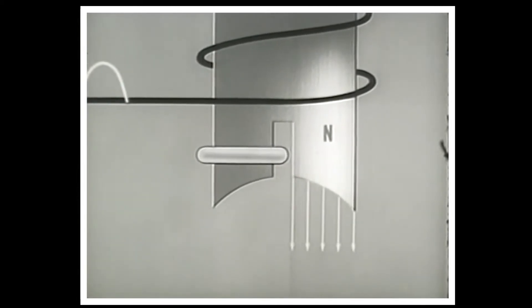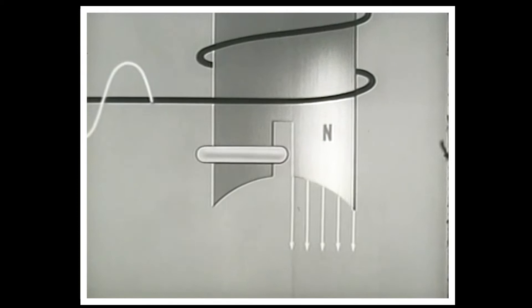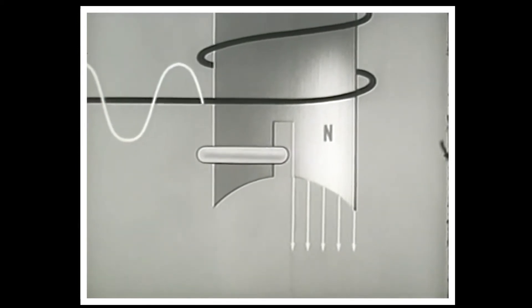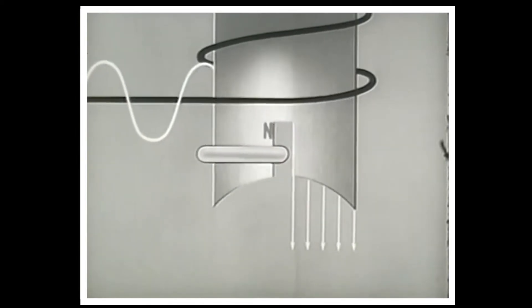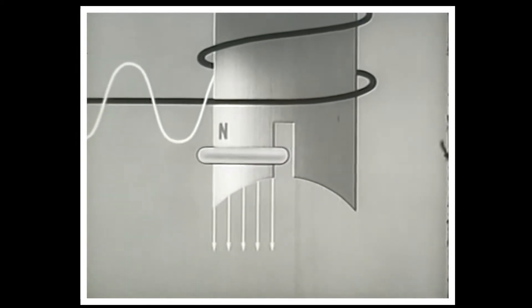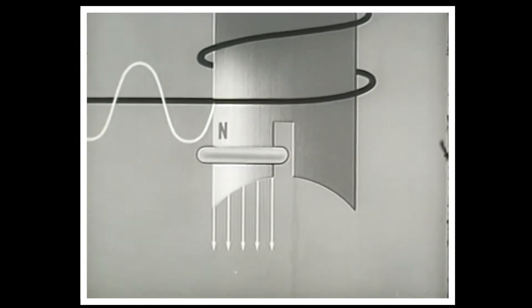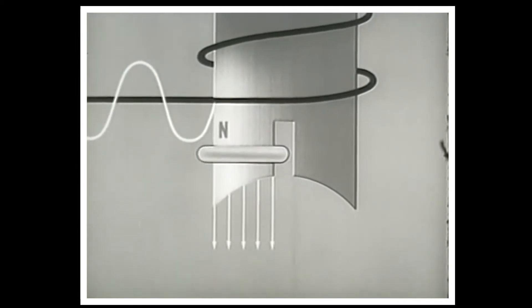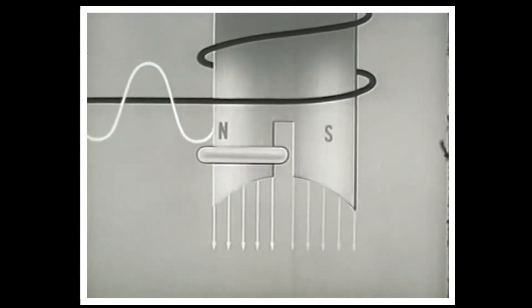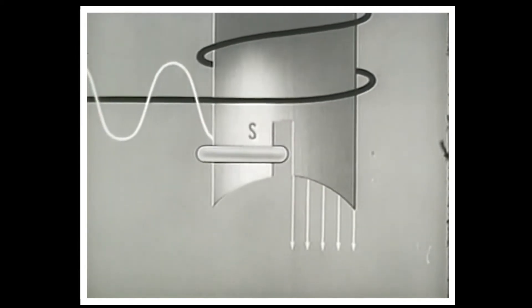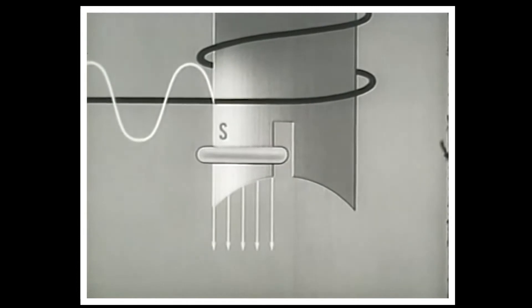Lines of force will emerge from the unshaded section of the pole face first. The inductance caused by the ring makes the shaded portion of the pole lag behind. This alternating pulsating action creates a phase difference within the pole.